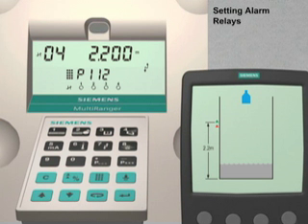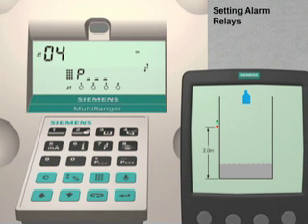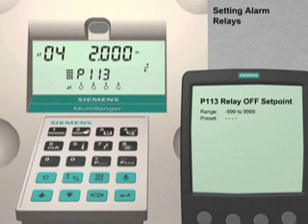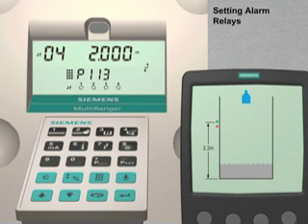Now we will enter the off set point value. Press the next display key. P dash dash dash is visible on the display. Enter 113. The parameter 113 setting for relay number 4 is currently a null value as indicated by the four dashes in the parameter index field. Enter 2 followed by the enter key to set the off set point value to 2 meters. We have now configured our high level alarm to come on when the liquid level rises above 2.2 meters and turn off when the liquid level drops below 2 meters.